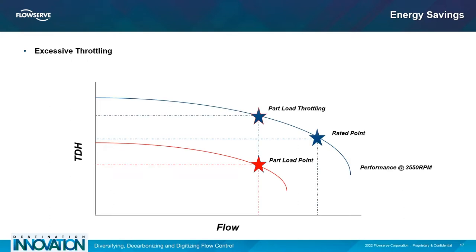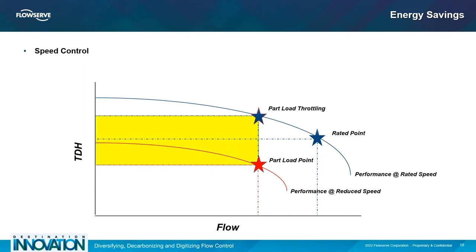For example, throttling on the discharge side of the pump would push the point of operation away from the rated point and farther back on the performance curve to a lower flow condition. This is represented by the part load throttling star. If any excess head were throttled downstream of the pump to achieve the part load operating point given by the red star, then the pump may cavitate excessively, experience internal recirculation, or any other mode of excessive wear and tear. A better option may be to slow the pump running speed to achieve a part load operating point with no to little throttling necessary. This would save the energy highlighted in yellow from becoming a destructive force against the pump, its seal, and the accompanying system.